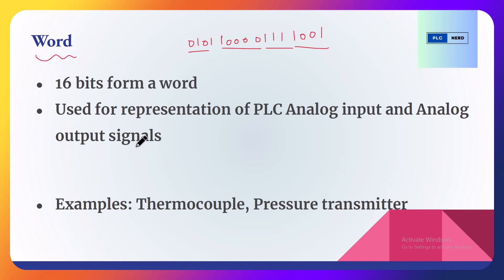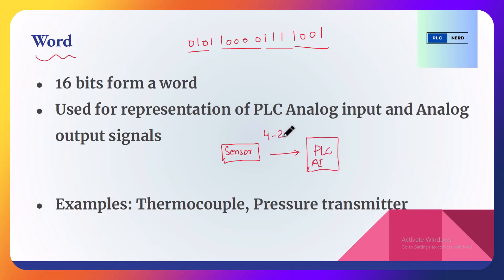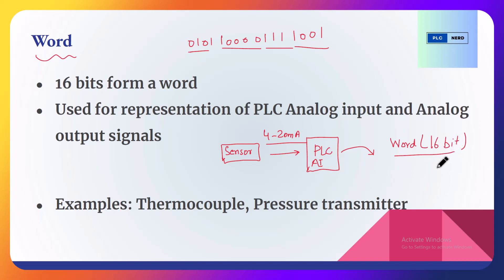For example, we have a thermocouple sensor interfaced with our PLC analog input card. Whatever milliamperes are coming from the sensor to the PLC analog input channel, the PLC will transform the 4–20 milliampere DC signal to a word — in other words, to a 16-bit value. Those 16 bits can then be further manipulated in our PLC program.